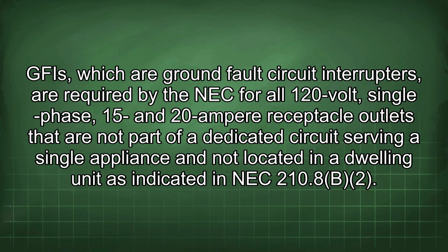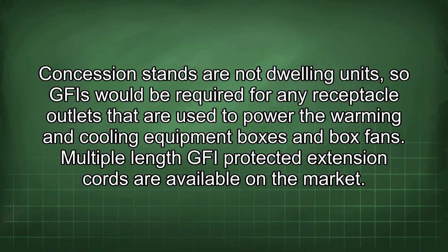GFIs, which are ground fault circuit interrupters, are required by the NEC for all 120-volt, single-phase, 15 and 20 ampere receptacle outlets that are not part of a dedicated circuit serving a single appliance and not located in a dwelling unit, as indicated in NEC 210.8(B)(2). Concession stands are not dwelling units, so GFI would be required for any receptacle outlets that are used to power the warming and cooling equipment boxes and box fans.